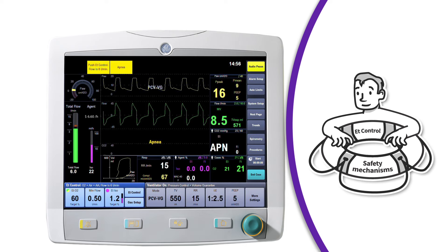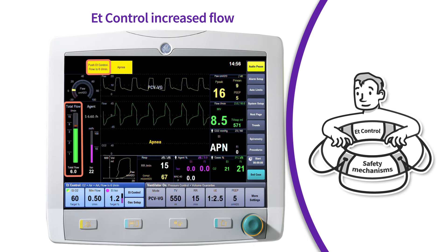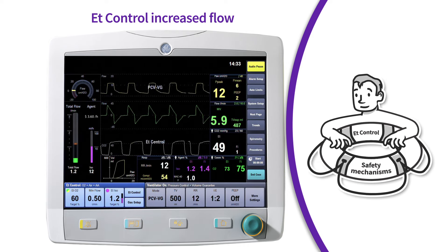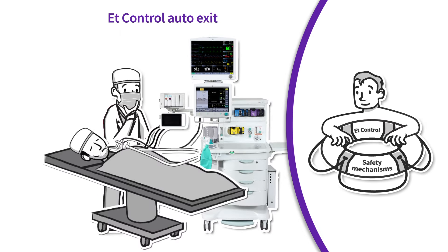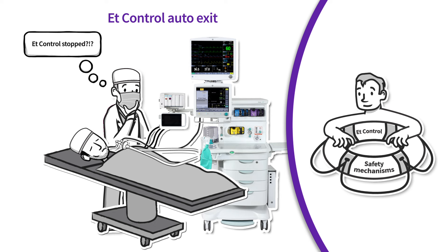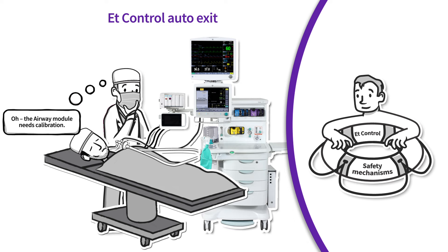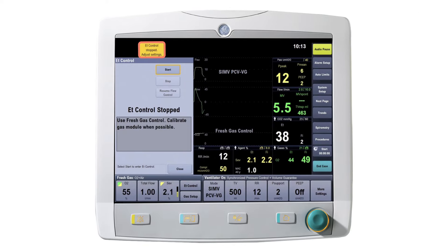With end-tidal control, there are safety mechanisms in place to help clinicians protect the patient. These include the delivery of increased flow when temporary issues arise, such as a leak — end-tidal control will automatically resume when the issue is resolved. Another safety mechanism is automatic exit from end-tidal control when an issue arises that requires clinician interaction or cannot be resolved during the case, such as an airway module calibration. When this occurs, the system automatically exits ET control and resumes fresh gas control. After an automatic exit, the anesthesia provider will need to manually re-enter end-tidal control.